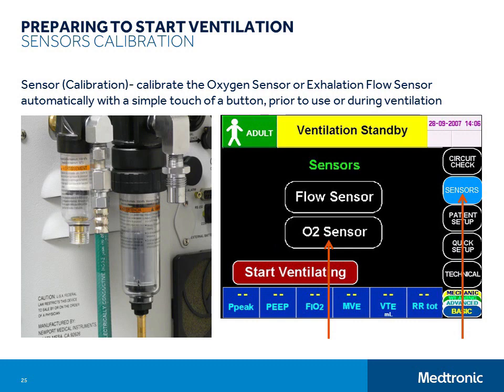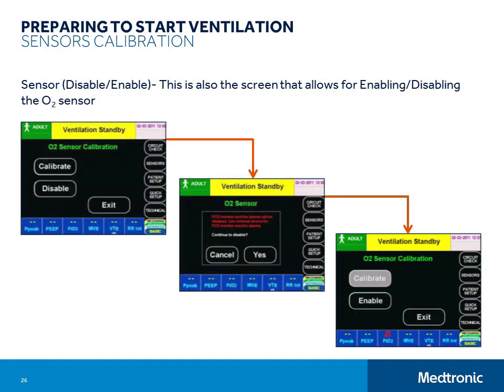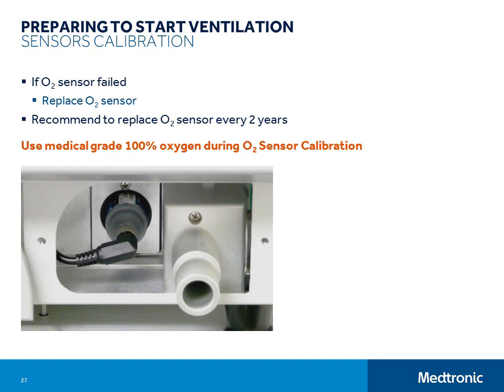You can calibrate the oxygen sensor anytime during standby condition or while ventilating, but you should keep in mind that 100% oxygen is delivered through the breathing circuit throughout the calibration period. So if your patient is being ventilated during the calibration, they will breathe 100% oxygen for up to 3 minutes. The pass or fail result of the O2 sensor calibration is logged in the event history.